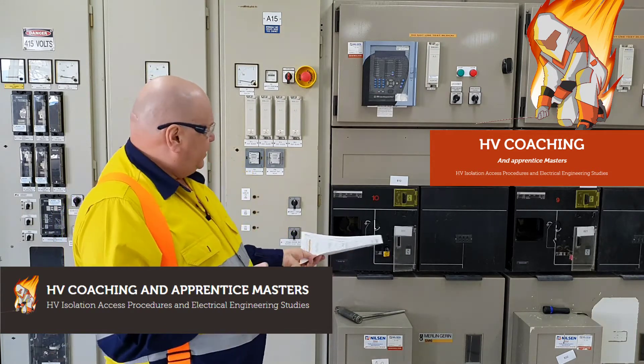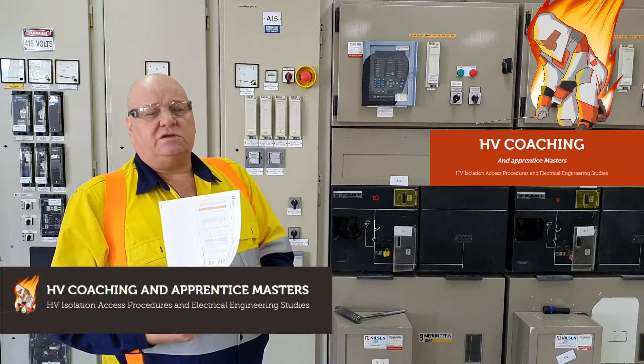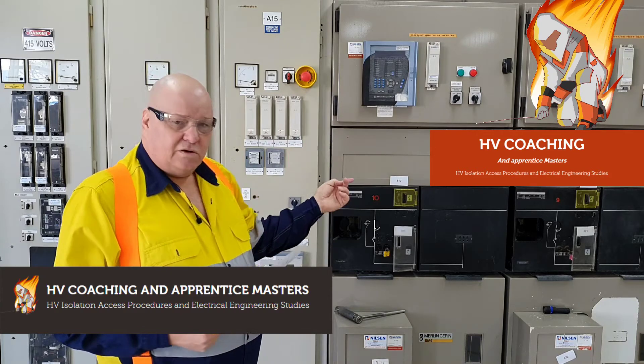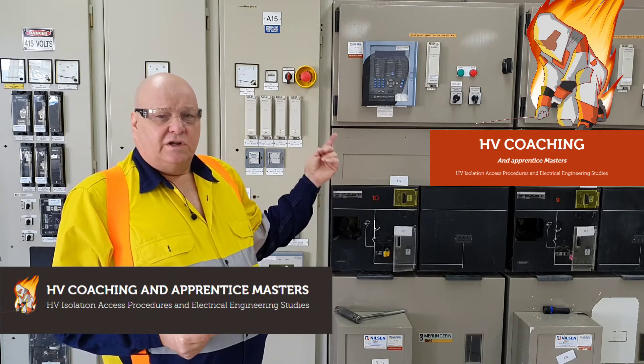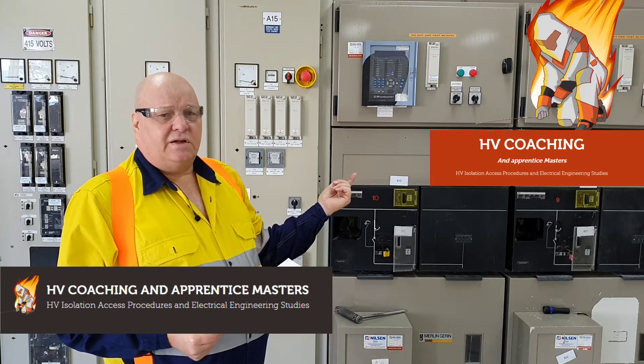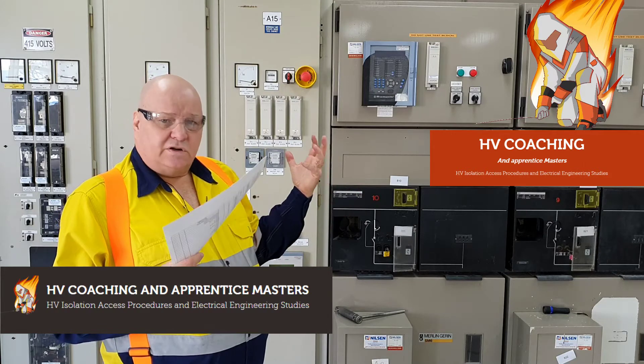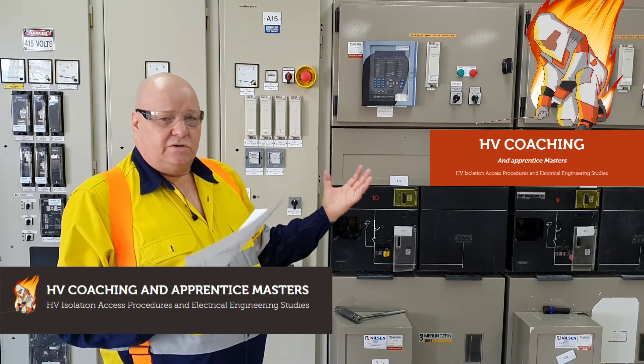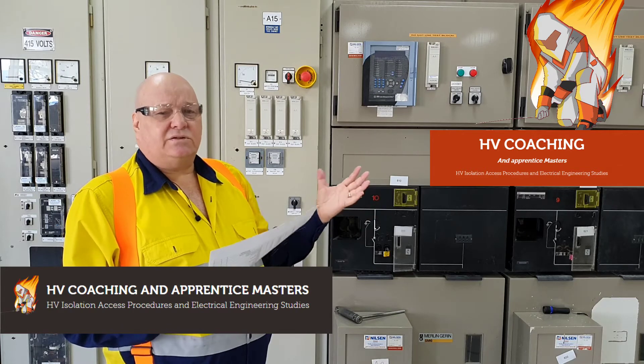All they have to do is press buttons and turn handles. It is the switching assistant or switching director who is making sure the correct equipment is being operated. When you've got that hood on, it's already a tinted shield. It fogs up. You've got safety glasses underneath as well — they fog up. Very hard to see what you're doing. You've also got big gloves on, so it is the switching director who makes sure that the switching operator does the right thing.